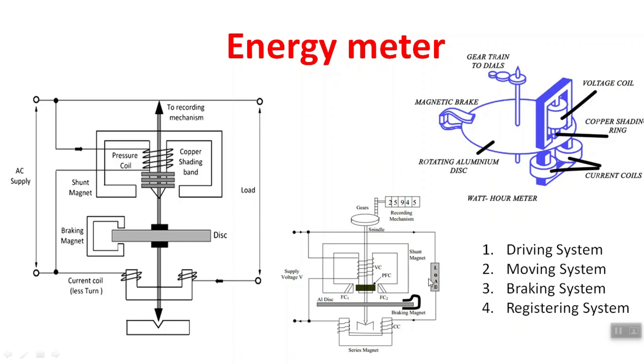Coming to the registering system: the aluminum disc is at the center of the spindle. The spindle is connected to the recording mechanism. The spindle is connected to a gear system, and the next gear connector is a cyclometer. The gears are connected one by one, and the total energy value is recorded. This is the complete operation of the energy meter.